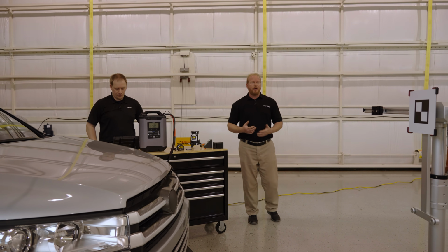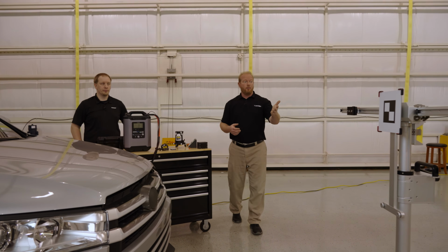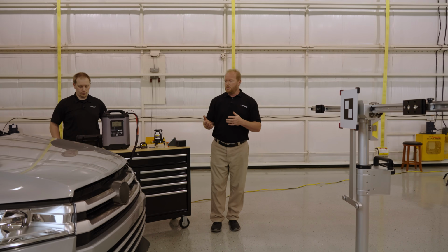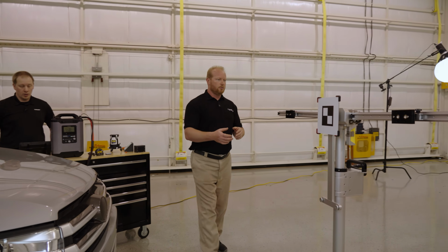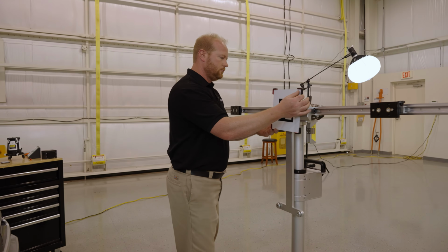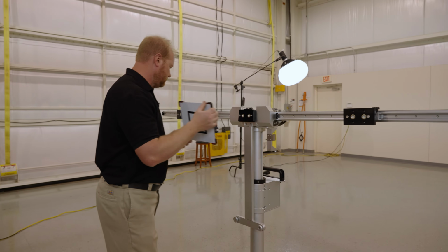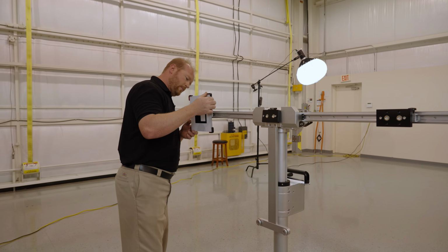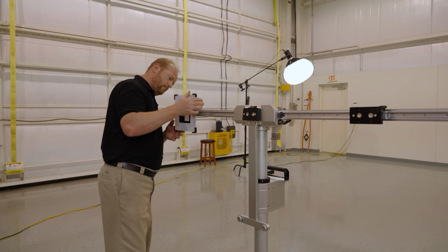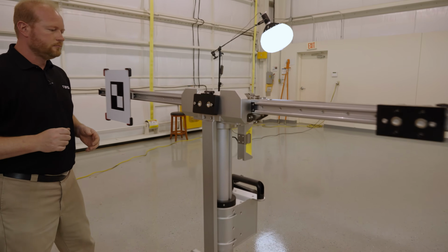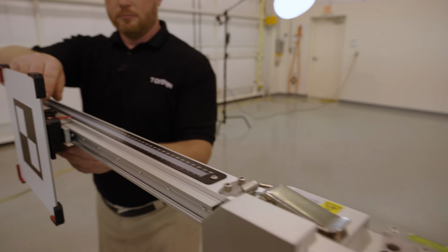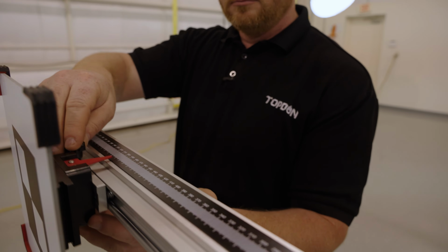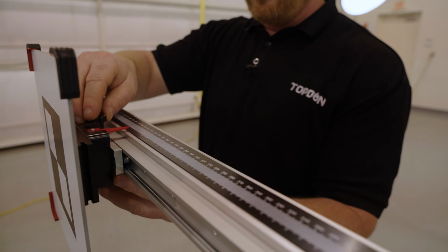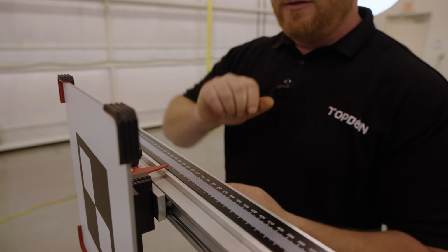So this is a 3-step calibration. We've already done the center calibration. Now we have to move this target. So what do we move this target to? Now the tool is directing us to move the target to the left position at 550 millimeters. And the frame here, Chad will show you, has a measurement on the actual arm, so you can see that you have it at the correct position. So we're going to go ahead and put that at 550 and get that in place.